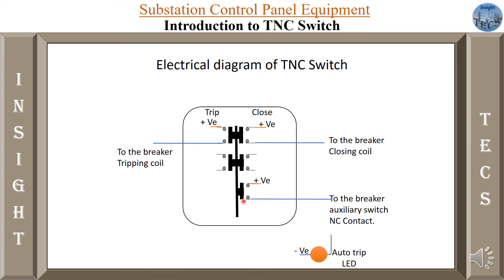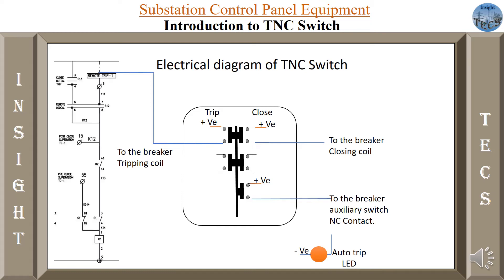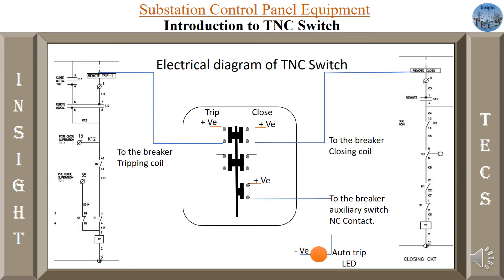Let us now see inside the breaker where these connections are made. Inside the circuit breaker, there is a tripping circuit where at terminal number 9 — remote trip 1 — we connect a wire towards the trip contact in the TNC switch. For the closing, we connect to the remote close in the closing circuit of the circuit breaker. That is how the trip and closed circuits are connected to the circuit breaker.